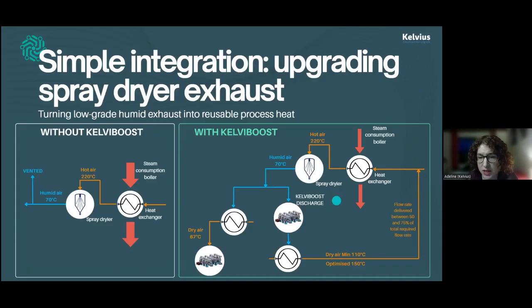On the right side, this is where we trigger the discharge of heat by sending the waste process heat stream—humid air at 70 degrees—directly inside our fleet of reactors. This corresponds to what we call the discharge. As you'd guess, charge is endothermal and discharge is exothermal. The temperature lift we provide is between the inlet and outlet of the reactors being discharged.